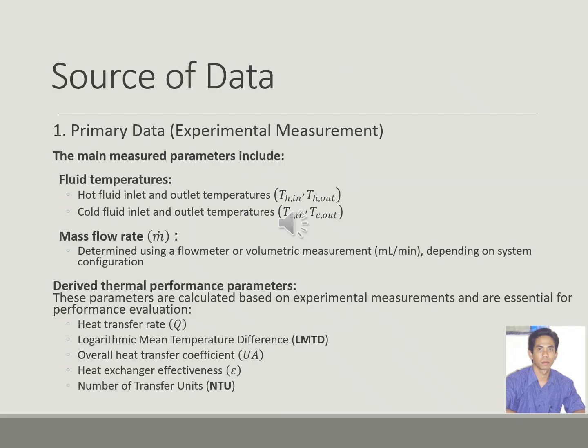Primary data are obtained directly from controlled experimental investigation of the designed micro heat exchanger system. The experiments are conducted under steady-state operating conditions, focusing on a low-grade thermal regime with a temperature range of about 35 to 45 degrees Celsius and a temperature difference of approximately 5 to 10 degrees Celsius, which are representative of low temperature heat recovery systems. The main measured parameters include fluid temperature of the hot fluid and also the cool fluid. And then the mass flow rate, which we determine using a flow meter or volumetric measurement, depending on the system configuration.